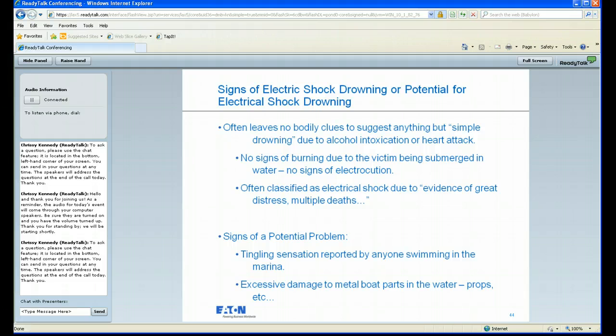Signs of a potential problem: if you hear anyone complain of tingling while being in the water, that electrical system needs to be shut down immediately. That's one of the first signs of a serious issue. It may be that the person hasn't come close enough to the source to really experience the full potential of that shock, or it may be that the boat or a piece of equipment has some characteristics that aren't working at the time, so they're not putting their full level of electrical current leakage into the water. Anyone complaining of tingling, that needs to be investigated right away.